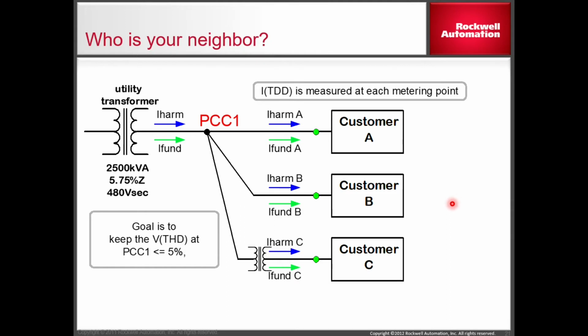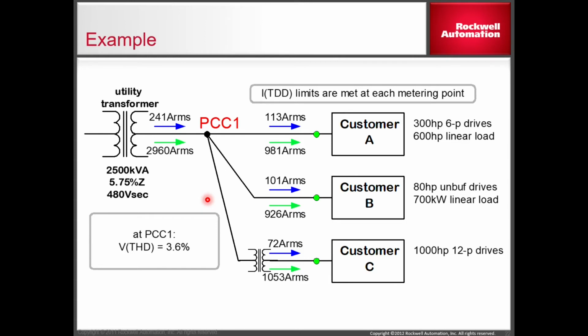And that's where we get into what you hear, the point of common coupling. The true point of common coupling, which IEEE 519 refers to, is right where the utility comes into your facility. Now, it may just come into your facility, or that utility transformer may feed several other customers. And that's one of the big reasons they want to keep that distortion under 5%, so you're not affecting your next door neighbor. In this example, once you do all the calculations, it comes out that we're at 3.6% of the voltage total harmonic distortion, and that is acceptable.